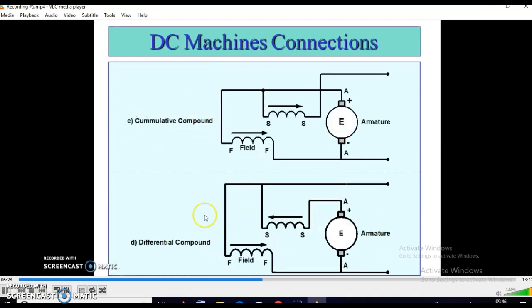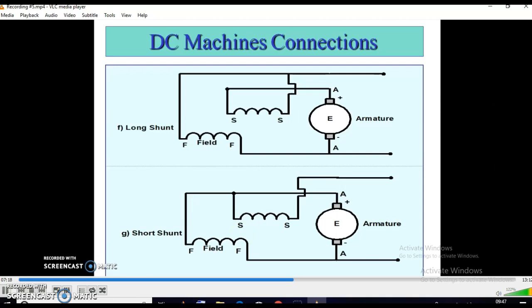Now, the compound excitation. If the machine has both series field flux and shunt field flux that aid each other, that means the resultant flux increases, the machine is called cumulative compound. Again, if the series field and shunt field flux oppose each other, that is called differential compound. These are classified as long shunt and short shunt based on construction.